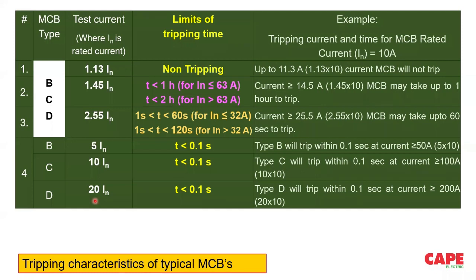For example, in a residential application, MCBs are to protect the wiring of the installation, not to protect your equipment. Now, in a residential application, in the distribution, especially in the final circuits, we are supposed to use the Type B MCB. Type B MCB is safer because it can trip instantaneously at even a lesser current. Even if the impedance of the circuit is a little bit higher, this MCB is efficient, because each of these instantaneous tripping currents is related to the impedance of the circuit. So Type B MCB is very much necessary for residential application.